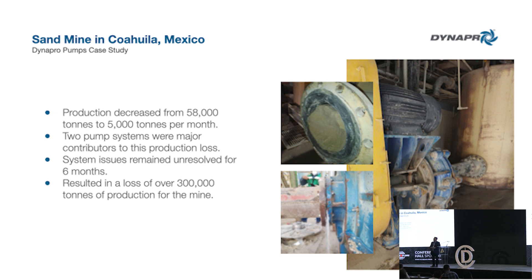I want to share a case study we did here in Coahuila — a sand mine. This shows how much a pump system can affect your operation. We were called into this operation; they had been running for six months and production had dropped from 58,000 tons a month down to 5,000 tons a month. We went in and determined it was two pump systems — they thought it was one — that were causing the production loss. It resulted in a loss of over 300,000 tons of production.